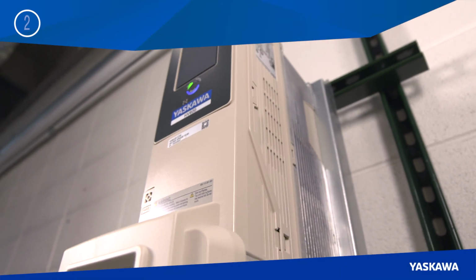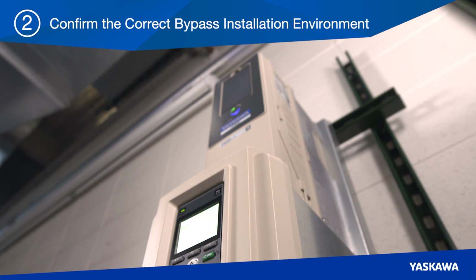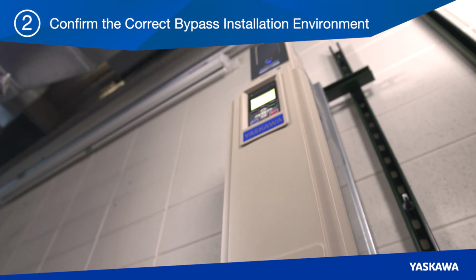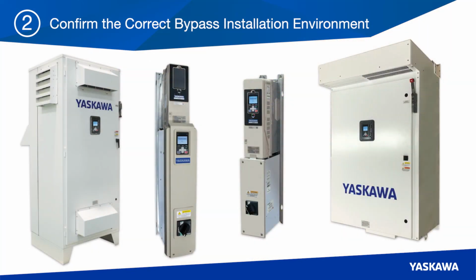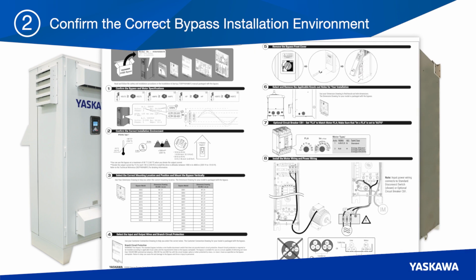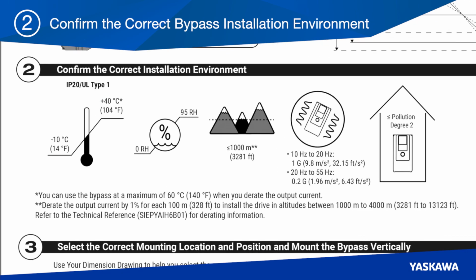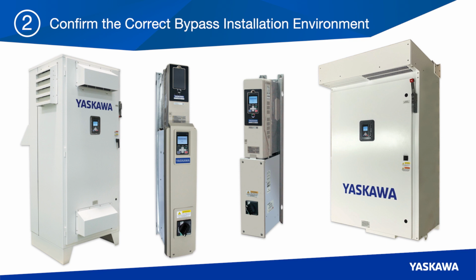Then, in Step 2, confirm the correct bypass installation environment. There are multiple enclosure types for the HV600 bypass with different ratings for environmental protection. The quick setup procedure shows environmental information for UL Type 1. If your enclosure type differs, make sure the environment is suitable for the enclosure type that you're installing.